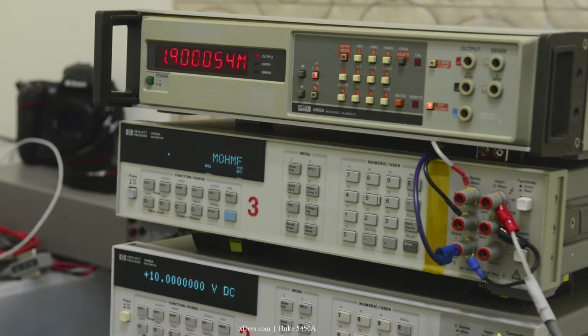Also, this 5450A instrument is not manufactured by Fluke anymore. It's an obsolete model and it's essentially replaced by the more expensive and heavier, but also more universal Fluke 5700, such as 5780A and 5730A. But essentially many of the ideas and the circuit arrangement from 5450 transitioned into those multifunction calibrators almost without significant changes. Of course, the relays will change to smaller-size latch-in relays, but the idea was pretty much the same.